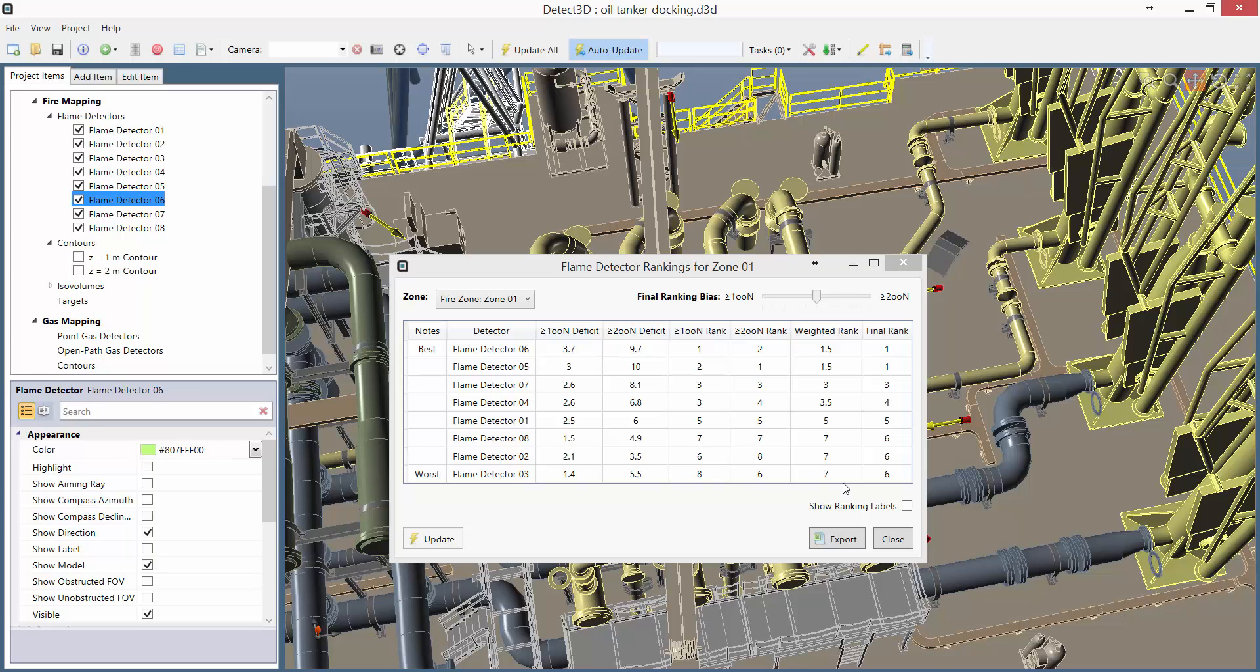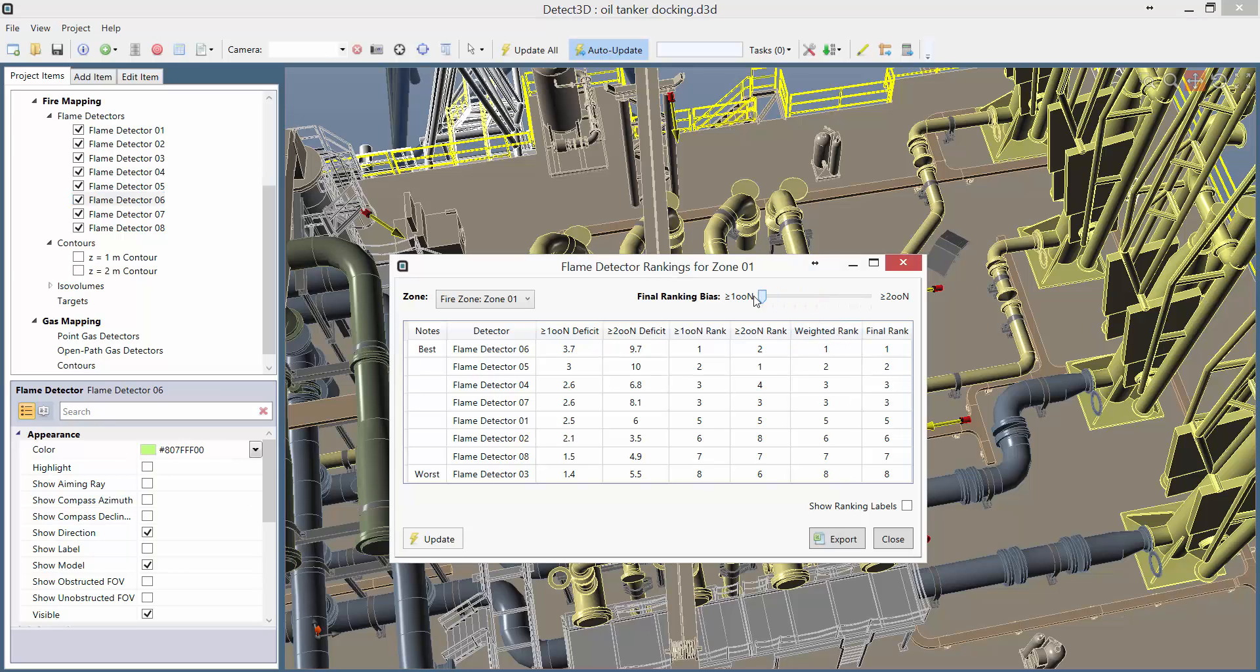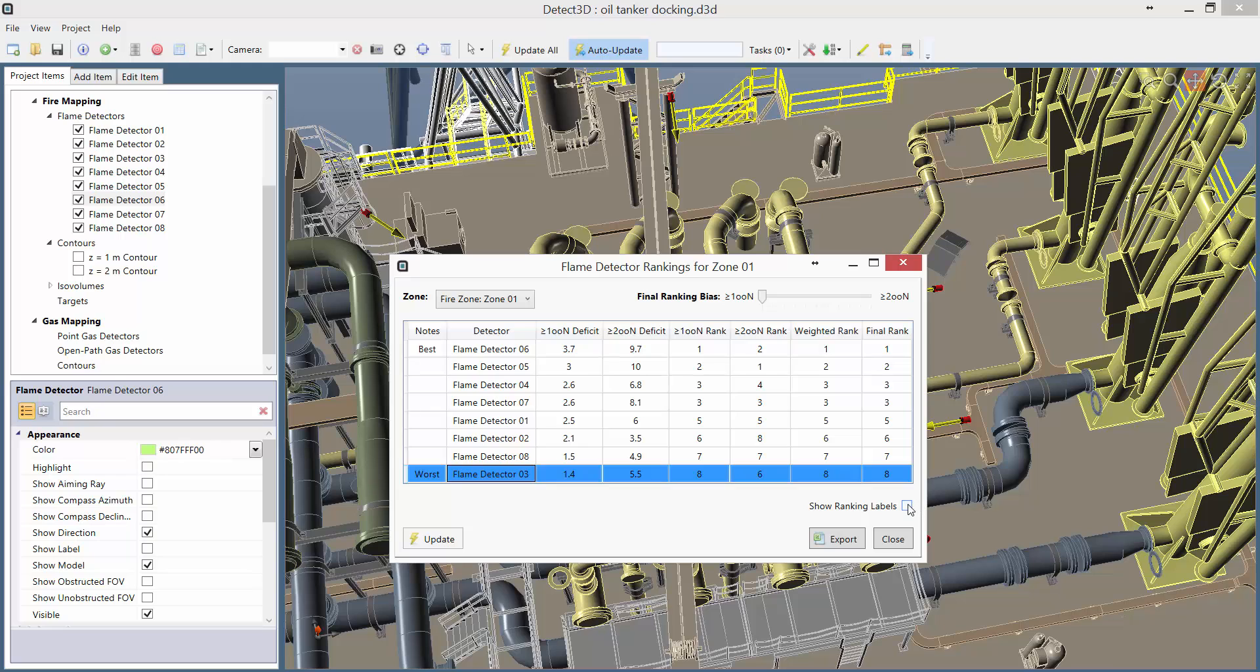The same thing is true for the 2 out of n coverage in the next column. The final columns show rankings of the 1 out of n deficit, the 2 out of n deficit, a weighted average of those deficits and then the final ranking. In this case we have an excess of 2 out of n coverage, so I'm going to bias the ranking to the 1 out of n deficit. We can see that Flame Detector 3 is the least effective detector for the 1 out of n coverage.